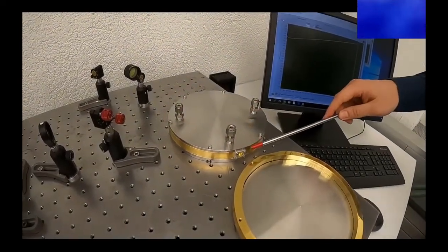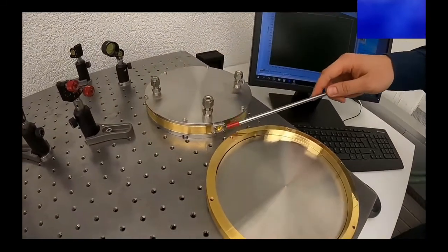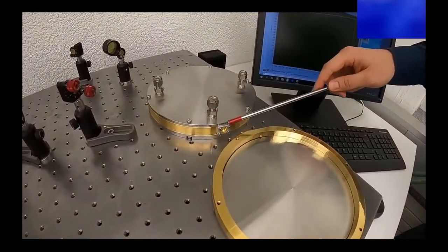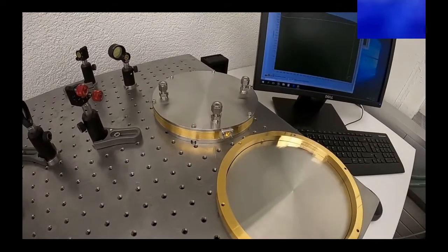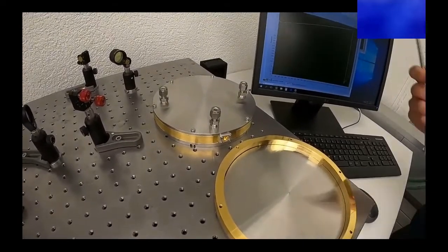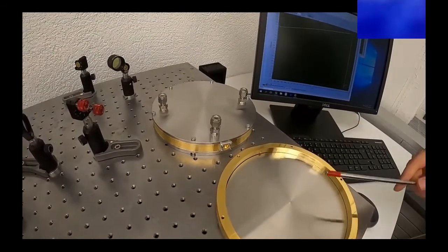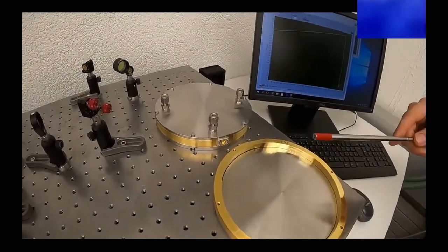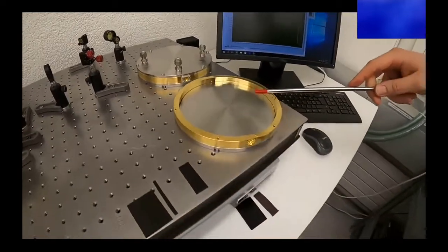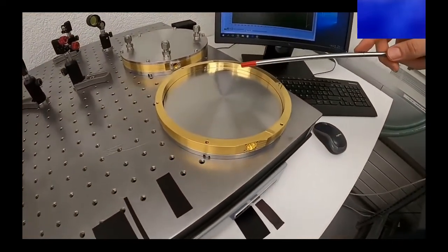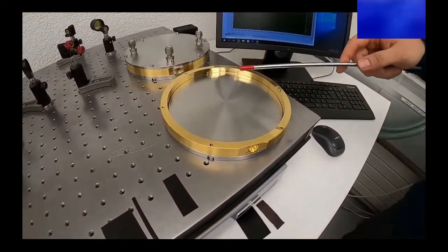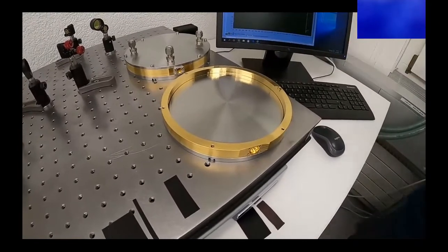Then for the input and output aperture, we have window holders, and here we basically mount half-inch windows of choice. We can do many choices, IR coating and wedged. Then this one, before assembling, is how you would use it when you actually set it up in your setup and you want to align it without the lid, and then you can just close it with the lid.